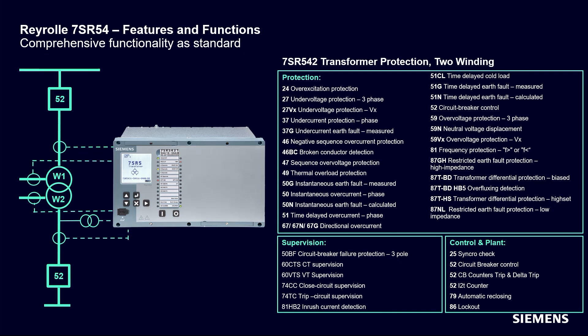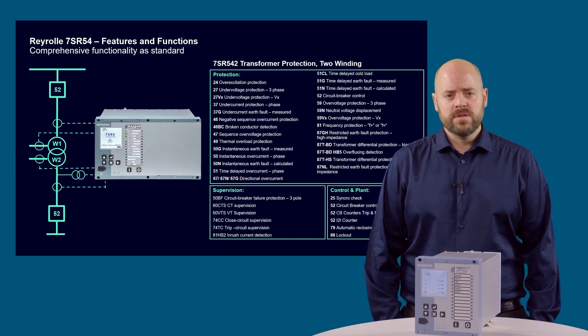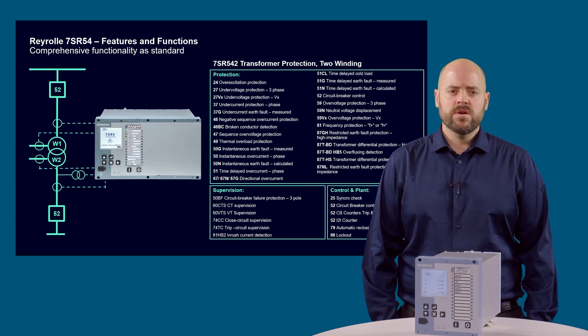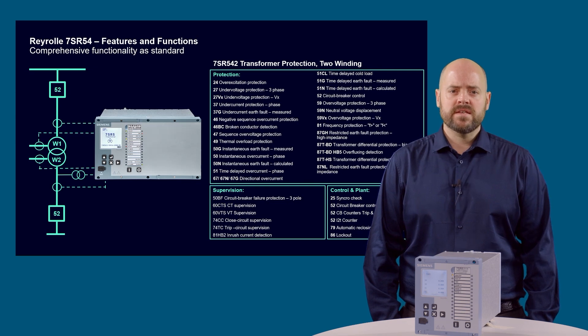To complete the scheme application, the device has the option for direct arc flash detection inputs with high-speed tripping contacts for fast clearance when arc faults are detected in enclosed switchgear, and temperature sensor inputs for connecting to sensors located in the plant.